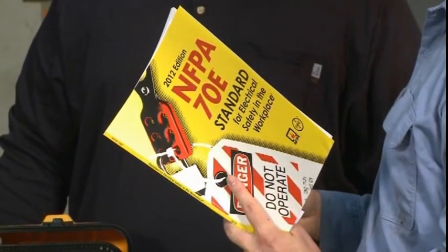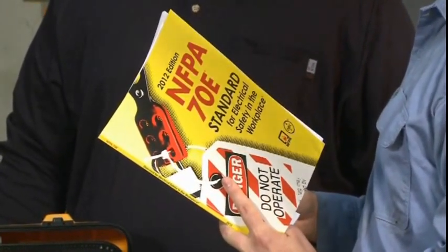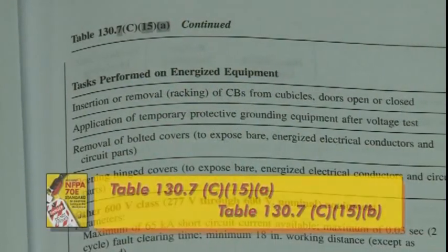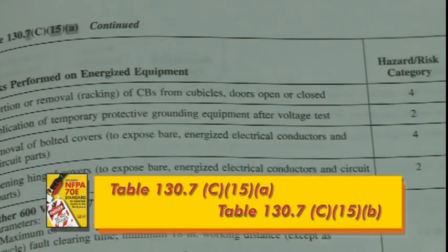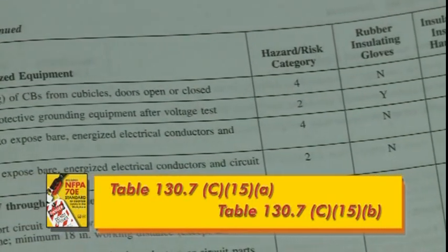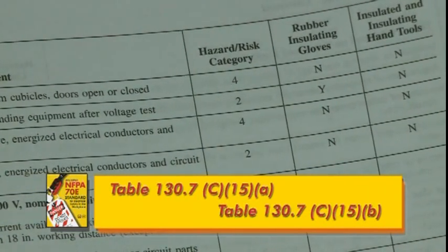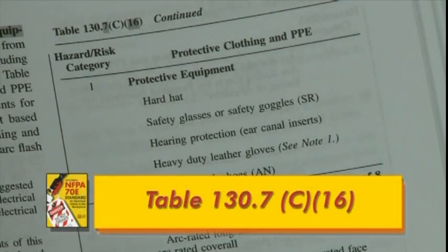The NFPA has established hazard risk categories. Each hazard risk category requires a specific level of arc flash protection measured in calories per centimeter squared, as well as other protective equipment. The NFPA has determined the hazard risk category for common electrical job tasks and listed them in Table 130.7 C15A and B. We will next discuss the arc-rated clothing and other PPE required for each hazard risk category. This information can be found in Table 130.7 C16.